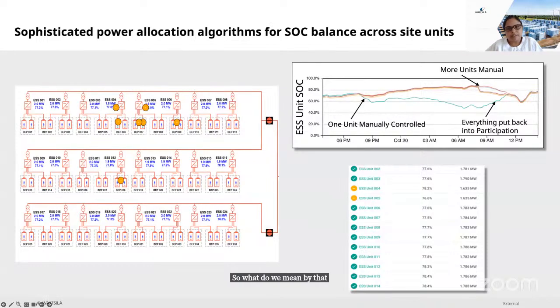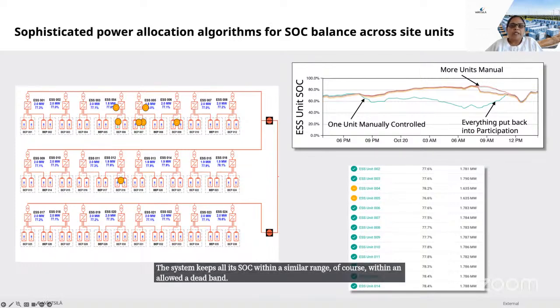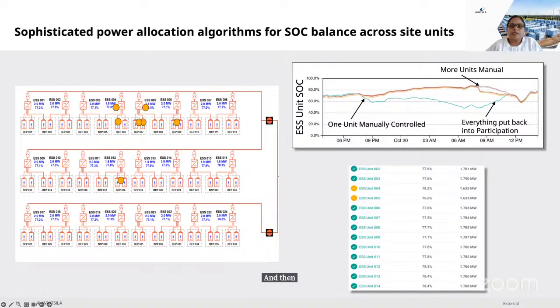What do we mean by that? This slide illustrates what a SOC balance-based allocation algorithm will do. While all the units are participating in the plant's auto operation, the system keeps all their SOC within a similar range, within an allowed dead band. Then, as units start operating manually, these SOCs deviate.